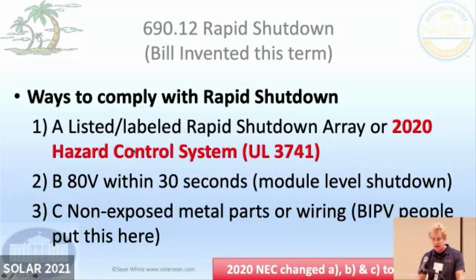It's possible to have 3 in series because they tested a wet firefighter with 3 modules in series and they were still okay. I mean, that's what the firefighter who was working on this told me. They changed some numbering here, but it's pretty much all the same. So keep your eyes out for this 3741 listed equipment. We'll see when more of that starts coming out.